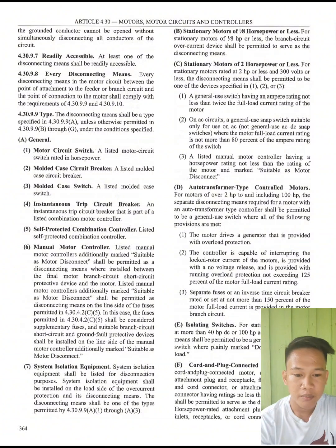6. Manual motor controller. Listed manual motor controllers additionally marked suitable as motor disconnect shall be permitted as a disconnecting means where installed between the final motor branch-circuit short-circuit protective device and the motor. Listed manual motor controllers additionally marked suitable as motor disconnect shall be permitted as disconnecting means on the line side of the fuses permitted in 430.52(C)(5). In this case, the fuses permitted in 430.52(C)(5) shall be considered supplementary fuses, and suitable branch-circuit short-circuit and ground-fault protective device shall be installed on the line side of the manual motor controller additionally marked suitable as motor disconnect.